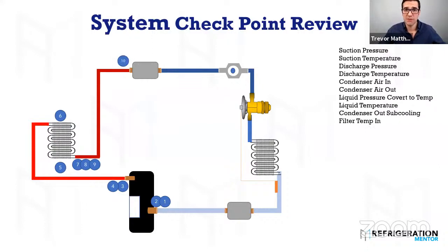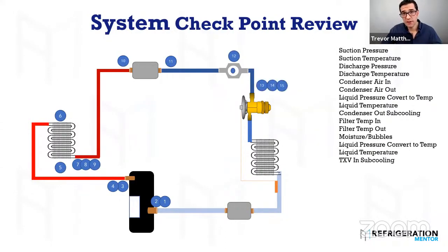Okay. You need to check your temperature in, check temperature out of your filter dryer. You could do pressure as well with temperature work. If you get 1, 2, 3 degrees, there's blockages happening, because there should be no temperature difference through it. You start getting a temperature difference, that means your filter's plugging up. You need to check if there's moisture or bubbles in the sight glass. So important. You need to check your subcooling at the inlet of the metering device. Did the temperature change? Did the subcooling change? If it did, what's going on in the liquid line? Is that filter dryer plugging up? You need to understand that, because now you're flashing at the TX valve potentially, and that's an issue.